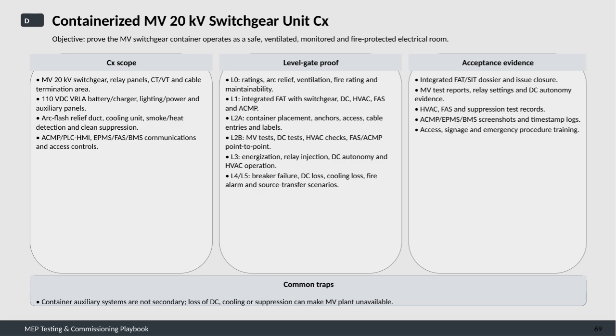Level 2 is split into two parts: the first confirms proper container placement, anchoring, access, cable entries, and labeling, while the second focuses on testing the MV system, DC system, HVAC checks, and point-to-point verification of fire alarm and control systems. Level 3 includes energization, relay injection testing, DC power autonomy, and HVAC operation.